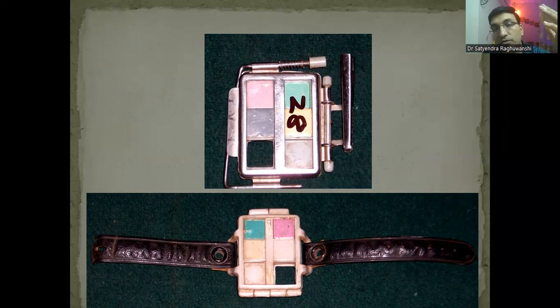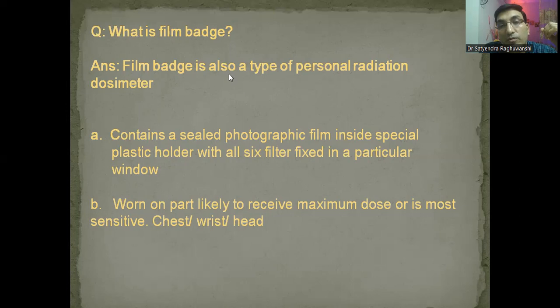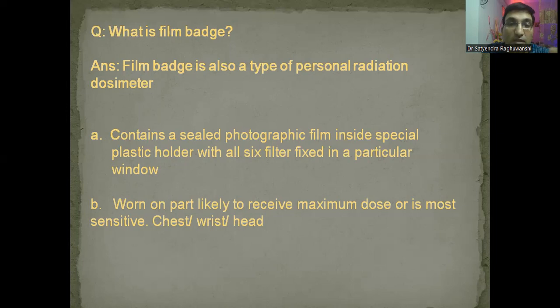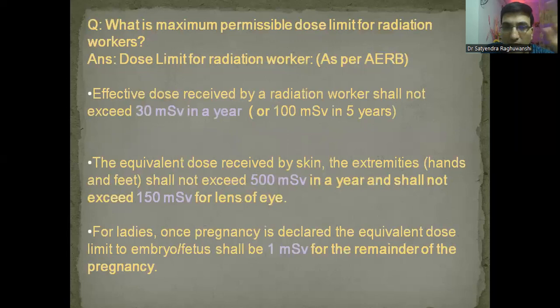Some candidates say 'sir, this is a wrist TLD badge' but it is actually a film badge. What is a film badge? It is a radiographic device for personal radiation monitoring. It is a conventional type of device with a sealed photographic film inside a special plastic holder and six filters. It can be used on the chest, wrist, or head level. What are the other kinds of radiation dosimetry devices? Film badge, pocket ion dosimeter, electronic dosimeter, or OSL — optically stimulated luminescence dosimeter.